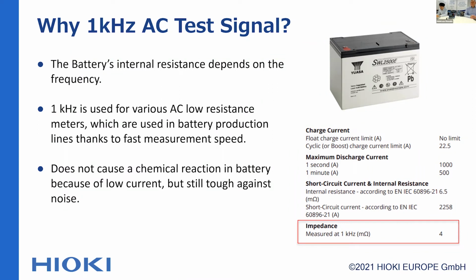This is important for the battery manufacturer and also for maintenance situations. As a result, the 1 kHz impedance has become the de facto standard for maintenance. When we look at the datasheet for lead-acid batteries, 1 kHz impedance is listed like this. The UPS manufacturer has a threshold as an example: if the AC impedance becomes twice the original value, the battery should be replaced, and so on. Please remember this as basic knowledge for the battery tester.